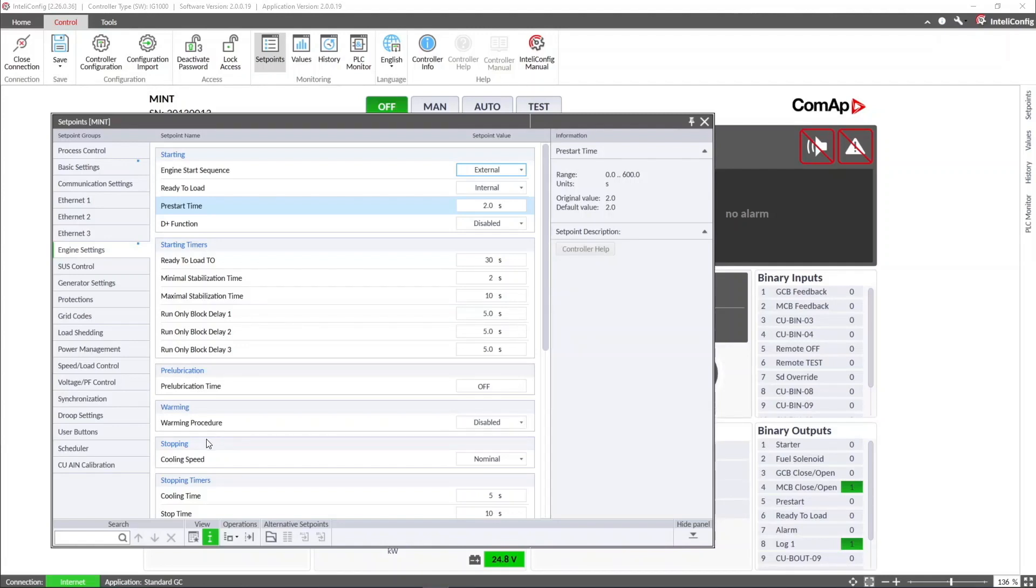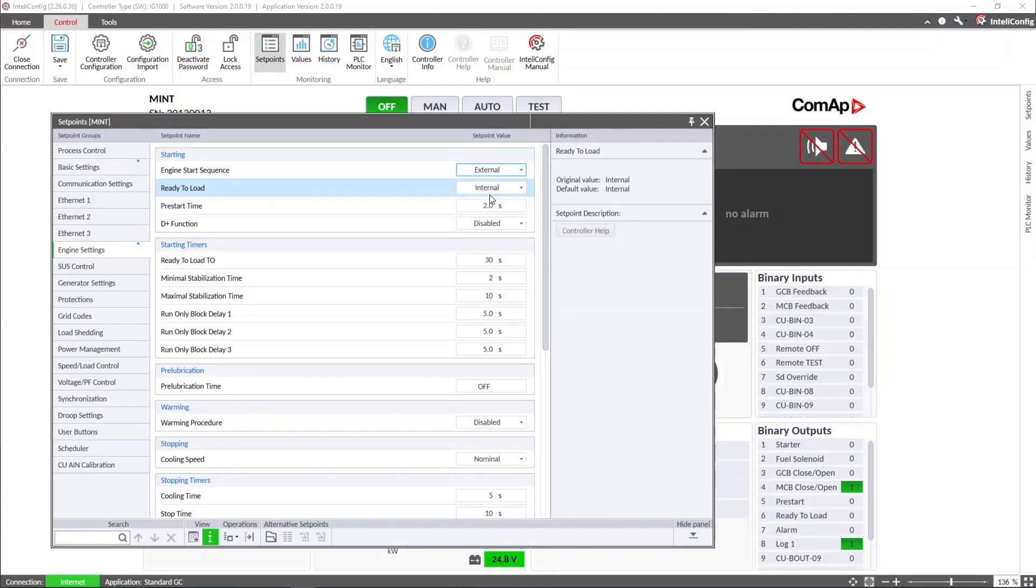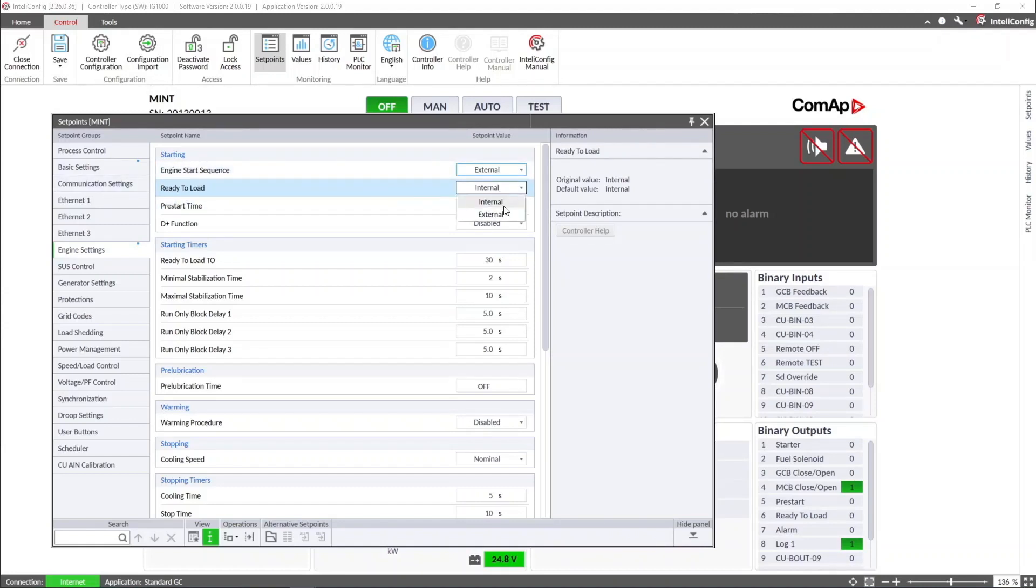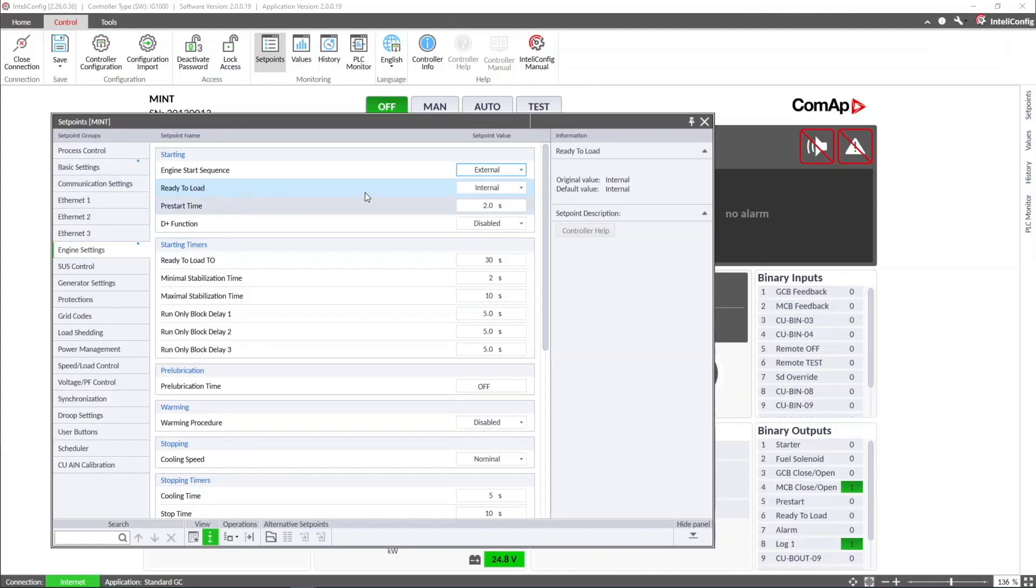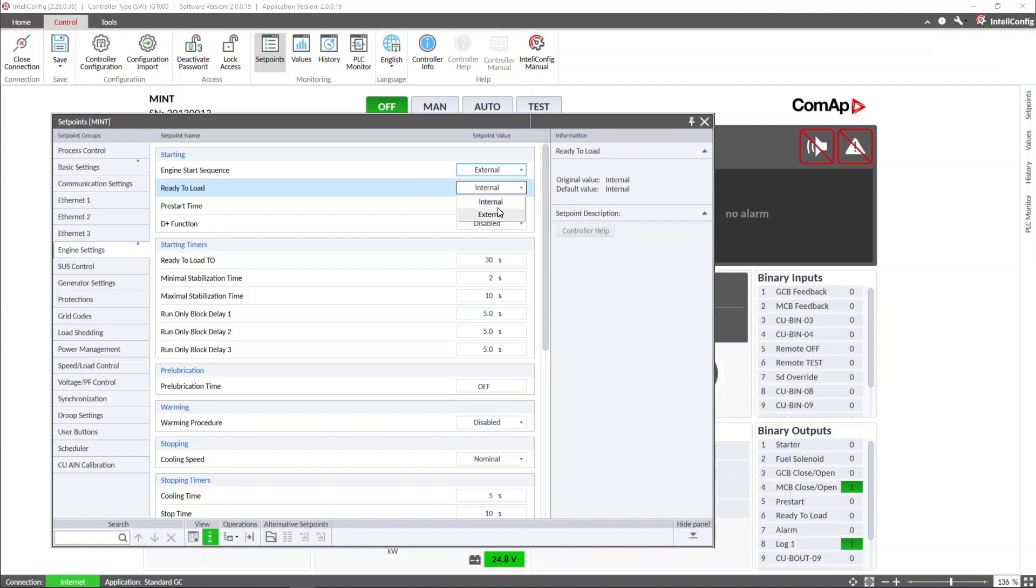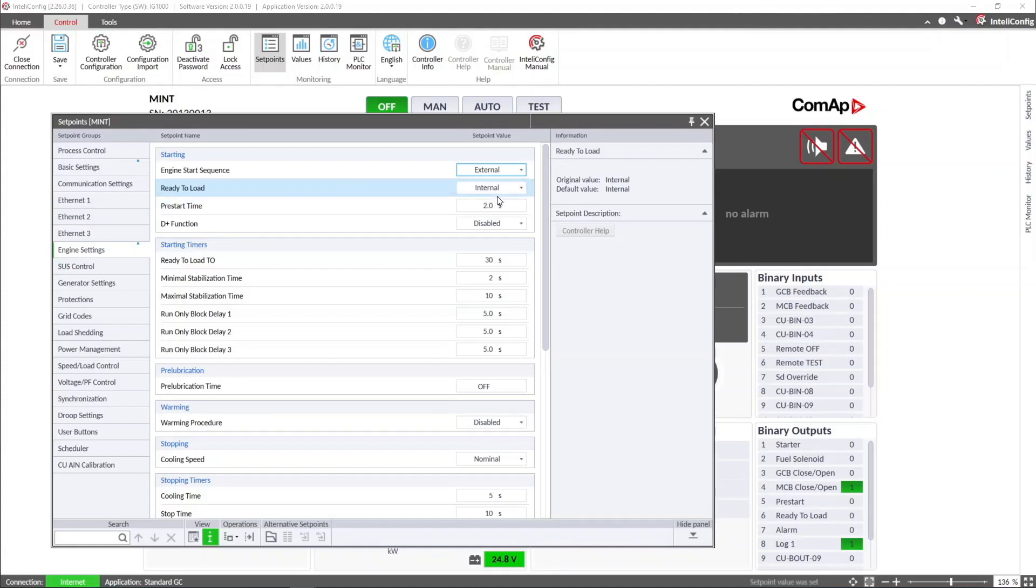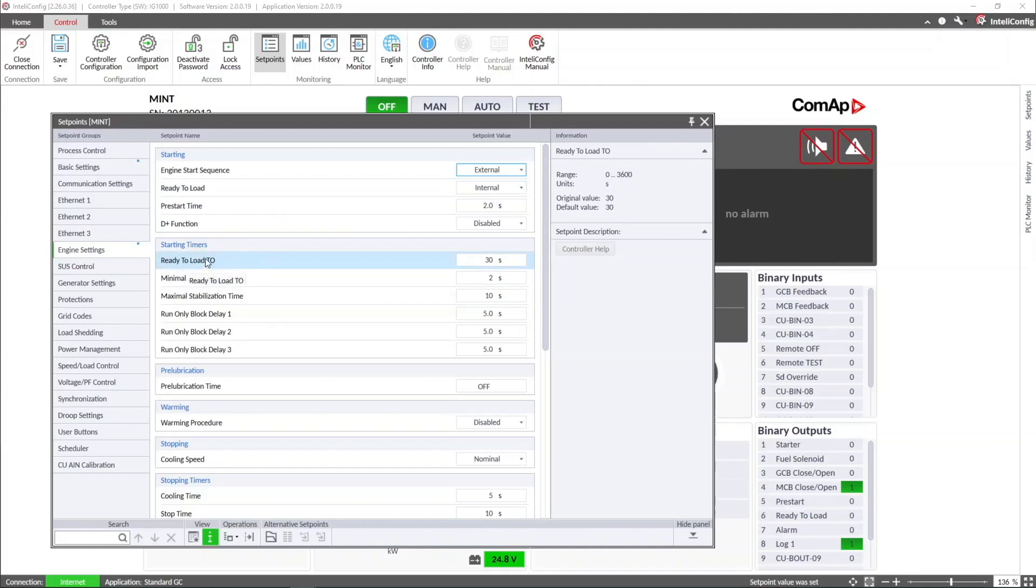We must also configure the ready-to-load setpoint, where we can select the source for the ready-to-load signal. It can be internal, which means that the controller will check voltage and frequency conditions before connecting the load. It can be external, which means that the controller should receive the ready-to-load status from an external signal connected to one of the controller binary inputs. We must also set a ready-to-load timeout, which will be the maximum waiting time for the ready-to-load input status.